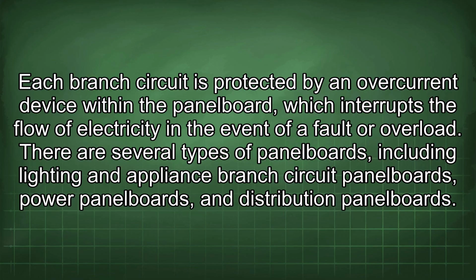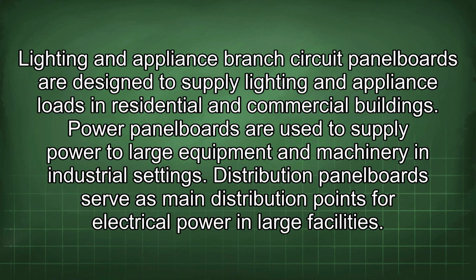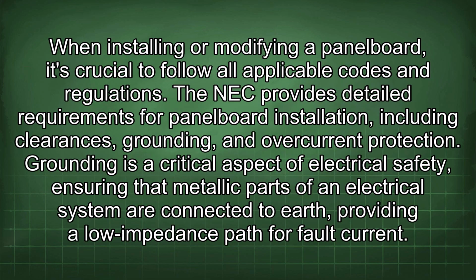There are several types of panel boards, including lighting and appliance branch circuit panel boards, power panel boards, and distribution panel boards. Lighting and appliance branch circuit panel boards are designed to supply lighting and appliance loads in residential and commercial buildings. Power panel boards are used to supply power to large equipment and machinery in industrial settings. Distribution panel boards serve as main distribution points for electrical power in large facilities. When installing or modifying a panel board, it's crucial to follow all applicable codes and regulations. The NEC provides detailed requirements for panel board installation, including clearances, grounding, and overcurrent protection.